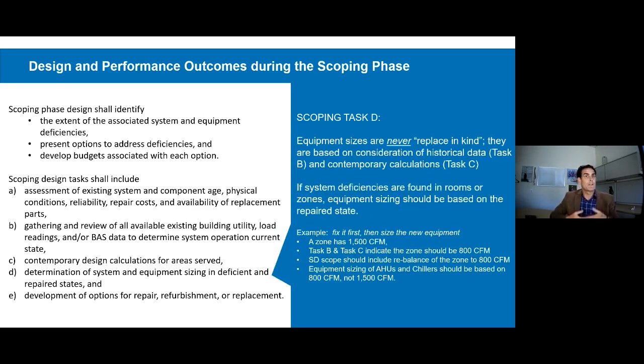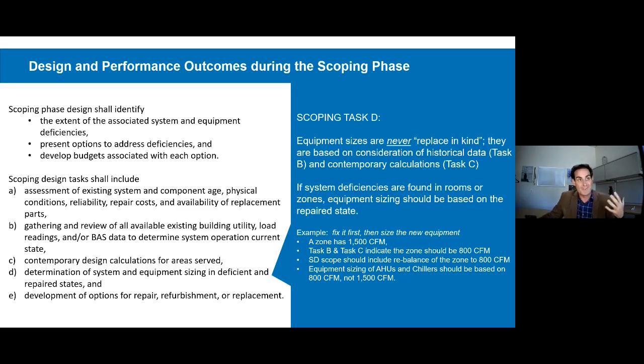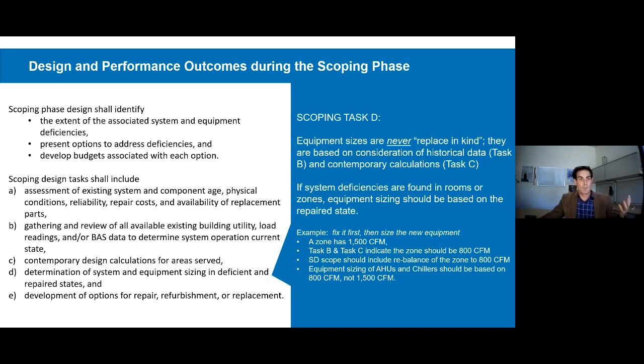Task D is determining equipment sizes. I'll point out that equipment sizing is step four on the list, which is to say that equipment sizing is not the first thing that we do. Saying that equipment is sized to replace in-kind is never acceptable. We want equipment to be sized based on the assessment of existing information and the contemporary design calculations — this is something that comes up time and time again in our scopes.